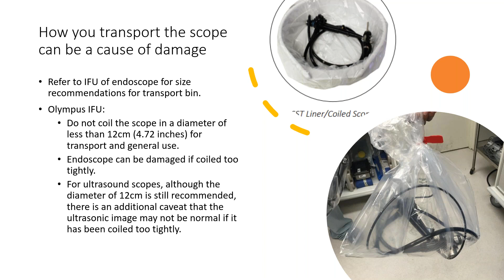And you'll see that Olympus IFUs actually tell us, do not coil the scope in a diameter less than 12 centimeters, because endoscopes can be damaged if coiled too tightly. And for ultrasound scopes, they might even impact the image quality of those endoscopes. And if you know what those are used for, they're used as a diagnostic tool and sometimes for interventional tools. So it's very important that those ultrasound scopes are working properly. So hopefully that right there is enough to convert you guys from the cinch sac maybe to a more rigid container, OSHA compliant container.